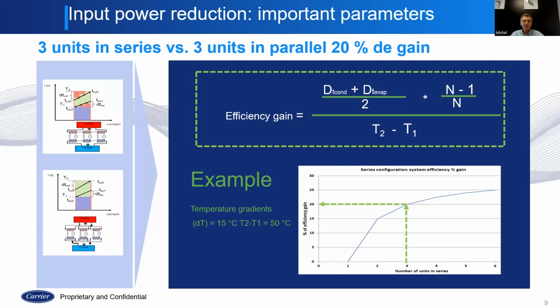And I'll give an example here. This is for district heating. If you have temperature differential on both sides of 15 degrees C - imagine 15 degrees C differential in evaporator, 15 degrees temperature differential in condenser, which depends on customer application and some other constraints, so it's not always possible - and in this particular case, the difference between high, let's call this condensing temperature and evaporating temperature, around 50 degrees C.